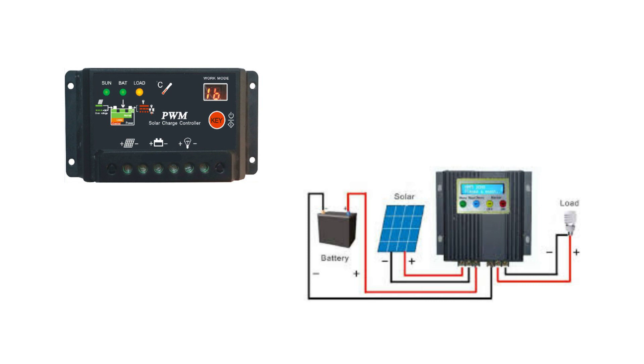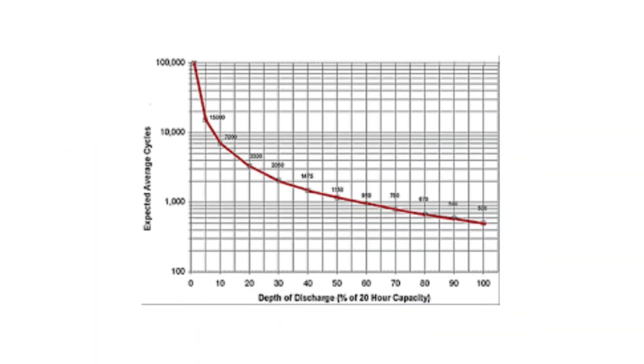The battery should not be drained completely — if it is drained fully, the number of charge cycles the battery can be used for gets reduced. A charge controller gives you control on protecting the battery; one can set a voltage at which the output from the battery is switched off based on a particular battery voltage. In the industry, the term DOD, or depth of discharge, is commonly used. The battery bank should therefore be designed above the capacity actually required — for instance, if two hours of battery backup is needed, the battery bank should ideally have three-hour capacity for the same power.